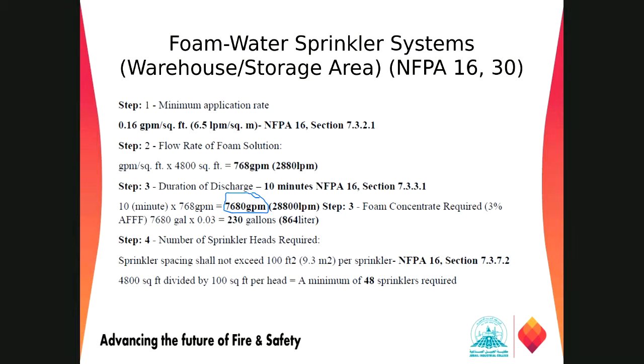Now we have step three, right? The foam concentrate required will be 3%. So multiplying 7,680 by 0.03, we need a foam concentrate of 230 gallons, right? 230 gallons, or 864 liters, for this application.